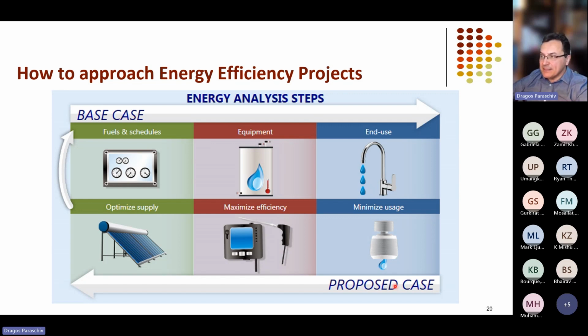So the savings that we look for here from avoiding this use in the end use range is only by identifying waste. For example, if you have the same set point in a facility during the unoccupied hours, you waste energy. You would be able to save energy by scheduling the set point accordingly.